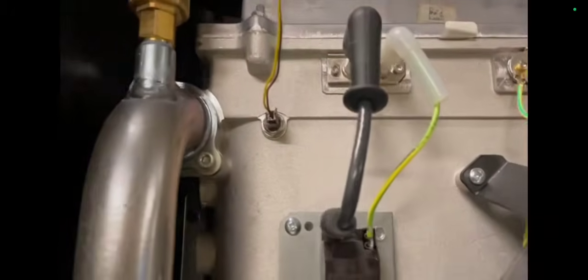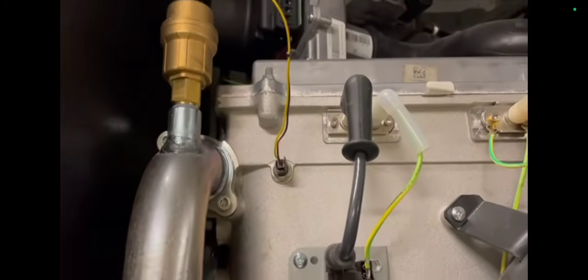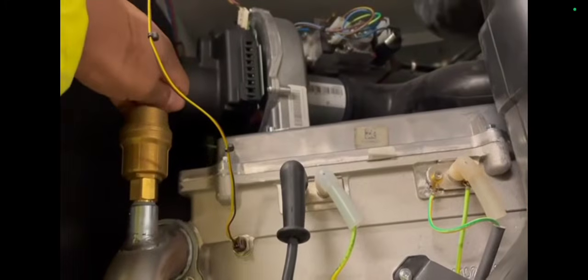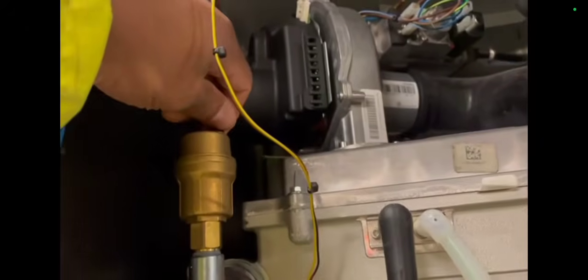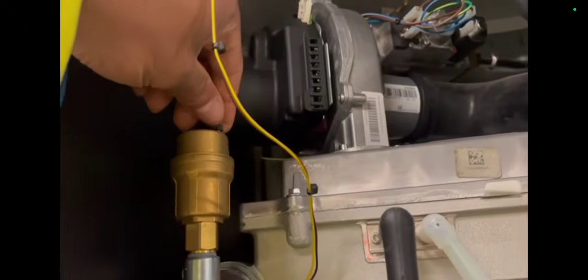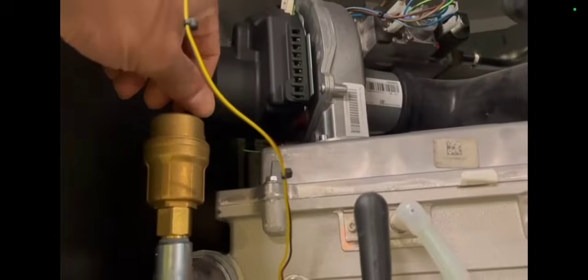So what I started with was I was going to focus on the condensate trap and on cleaning the probes. I had no spare probes, so I thought I would clean the probes. Whilst I was inside the case, I also vented the boiler because the manual vent seemed to be closed. So I opened that up.